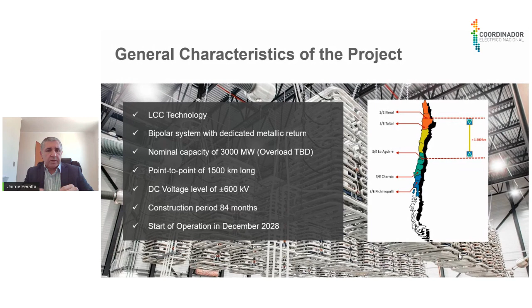Well, here are some of the justifications of the main characteristics. Basically, at 3,000 megawatts, why not greater? Well, going higher capacities like 4,000 megawatts, we really start seeing an increase of the operational risk in the system. We have to bear in mind that the peak load in the Chilean grid is 10 to 11,000 megawatts. So having 40% during peak demand, which could actually be 70% during a minimum load, starts to introduce an operational risk, which indicates that something happened to that line.